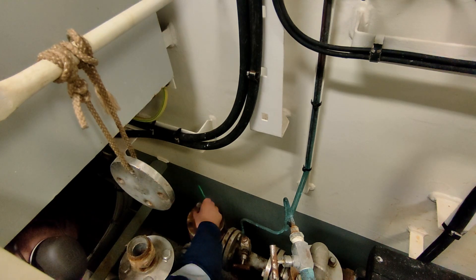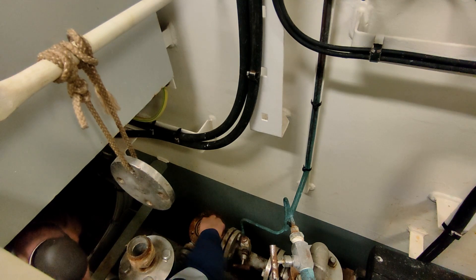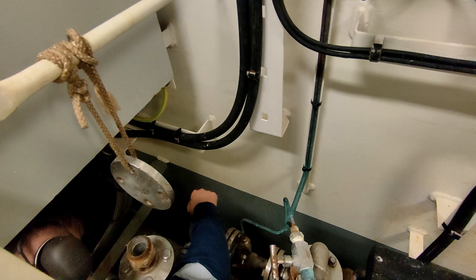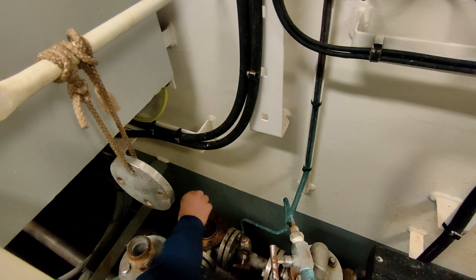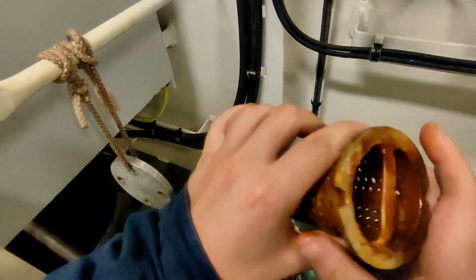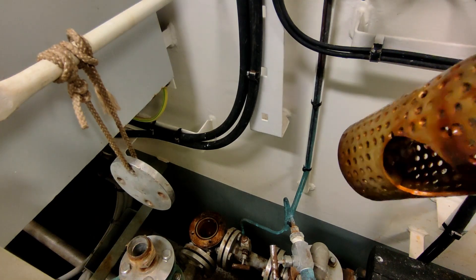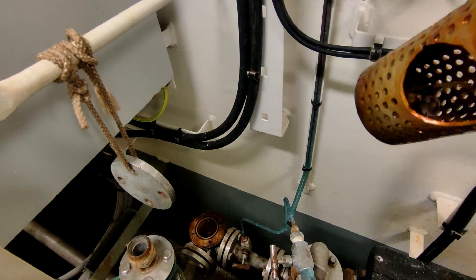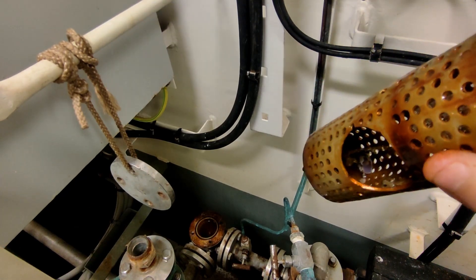I'm just trying to lift the lid off. So there's the O-ring you can see. And I'm just going to lift the filter housing out. Let the water drain back into the housing. And I'll hold this up to the camera. I don't know if you can see in there. Got a little bit of plastic in there, looks like tape or something. I'm going to take this, wash it out, refit it. So I'll be back in a minute.